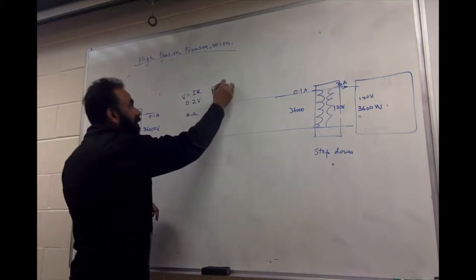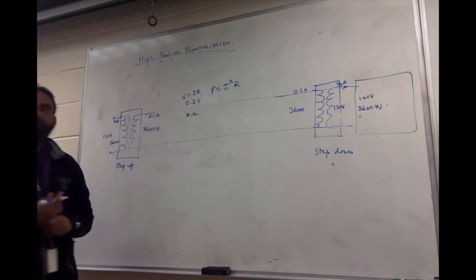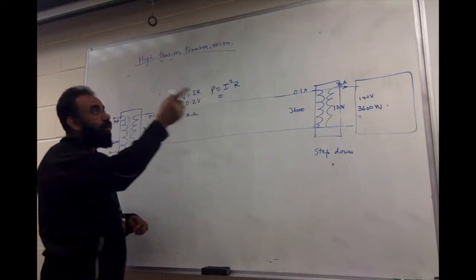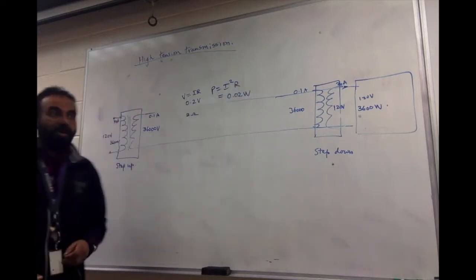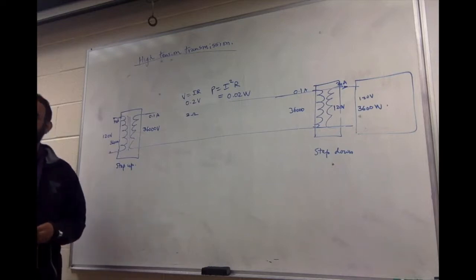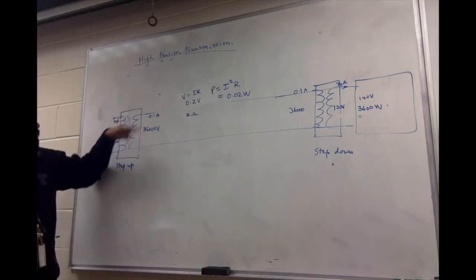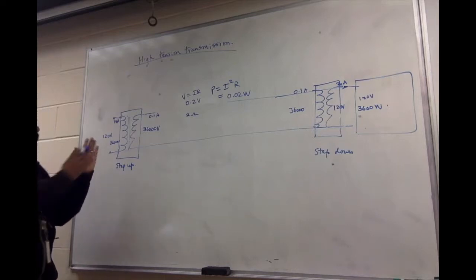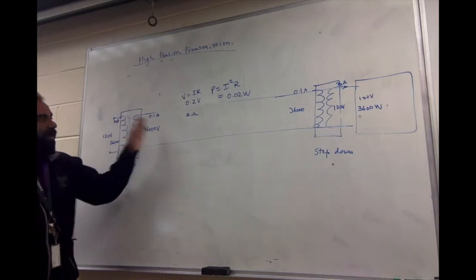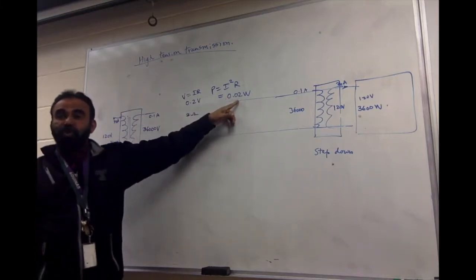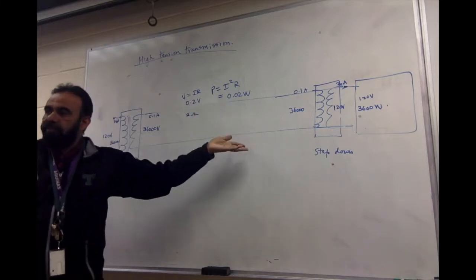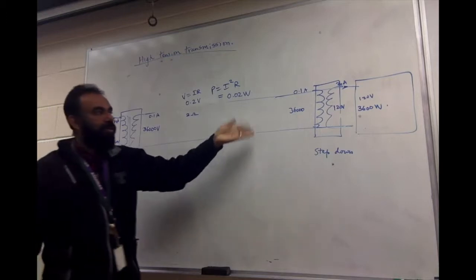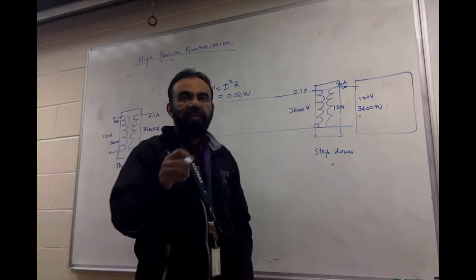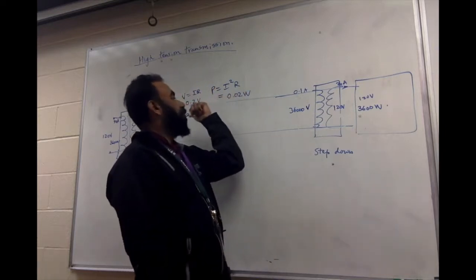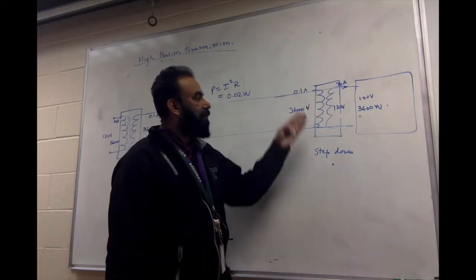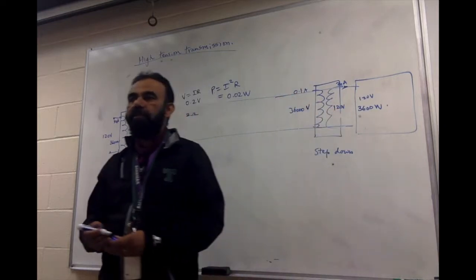What about power loss? Power is equal to I squared R. I is 0.1, 0.1 squared is 0.01. So it's basically 0.02 watts out of what? Out of 3,600 watts, because power is exactly the same, multiply this and this, you get the same power. Power is transformed, so power is not going to be different. So power is 3,600, out of that 0.02 watts you're going to lose because of the heating in these wires, which is negligible. So when you go to this point, you still have literally 36,000 volts there, the loss is 0.2 volts, which is nothing at all, and the current is 0.1 amperes. So when you transform it, you still have 120 as the output.